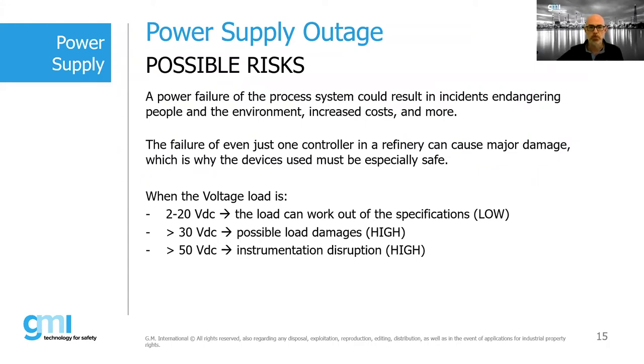The second dangerous failure condition of a power supply is when the output voltage reaches a value higher than 30 volts. In this condition, the load is subject to extra voltage, and we can damage it. Or in case of output voltage higher than 50 volts DC, the field instrumentation can suffer a definitive disruption. We can take, for example, an engine cooling system which works thanks to a standard power supply. Suppose that this power supply fails and goes into an overvoltage condition, damaging the cooling system. This will lead to an overheating of the engine, which will lead to serious consequences for the whole system connected to heat. Once again, I want to underline the value of having a separate power supply system, which guarantees high performance and safety.